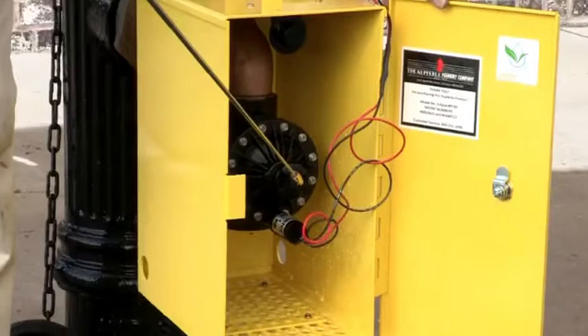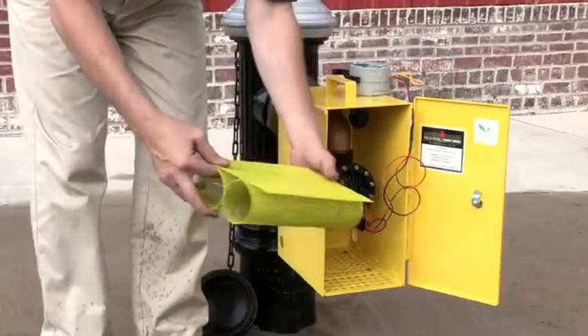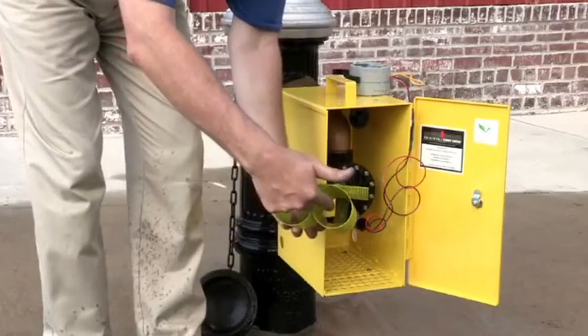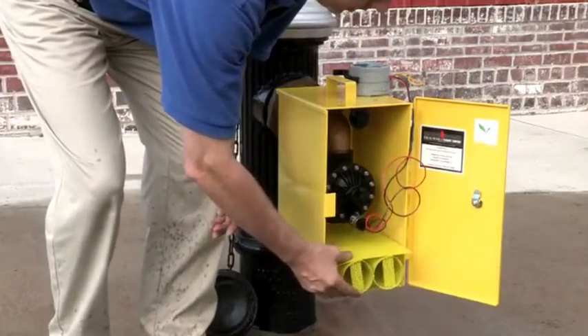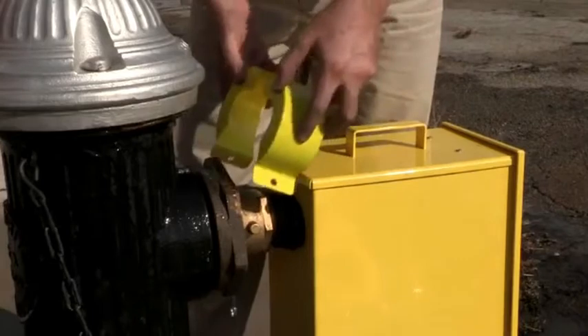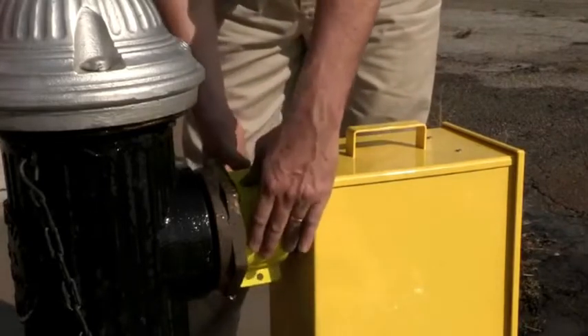The adjustable solenoid-operated 2-inch diaphragm valve opens and closes slowly to avoid water hammer. Some optional features for the Eclipse 9700 include a custom dechlor basket for tablets, a collar lock to avoid vandalism, and a sampling point bib.